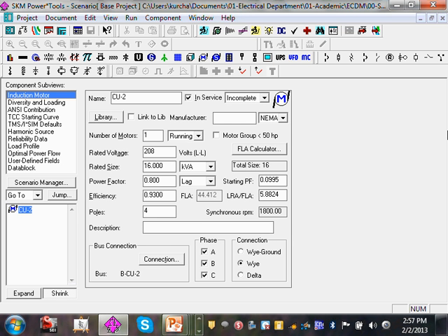The reason why you model all your equipment, as you guys are familiar, what happens to the motors if you have a short circuit in your building? Absolutely, momentarily, all your rotating equipment, anything that rotates, instead of sucking current and power out of the system, turns into pushing power into the short circuit connection. So they contribute to the value of the short circuit. All your air handling units, chillers, rooftop units, exhaust fans, all of these rotating equipment also push current, typically equivalent to their locked rotor current. That's the rule of thumb that we use. So if a motor is a 100 amp motor, and roughly 6 times this is the locked rotor or start current, they will be pushing under short circuit condition 600 amps into that point of short circuit. So they contribute to the short circuit.